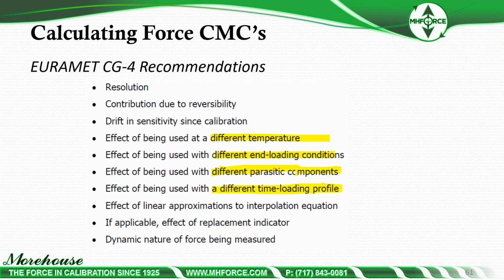Again, if you're going to a lab, a company that's just taking up and down readings and does not have a dwell time, or just doing like 1 or 2 seconds as opposed to 30 seconds, there's going to be a difference in output. I have a little presentation I gave to E74 committee on that, and at times it can be significant. So effect of linear approximations to interpolation equation, if applicable, effect of replacement indicator, dynamic nature of the force being used there. That's very hard to quantify, but they put it in there. As I said, they put lots of things in there.